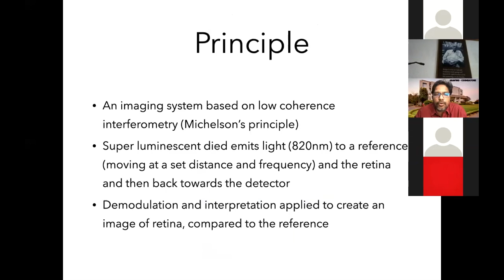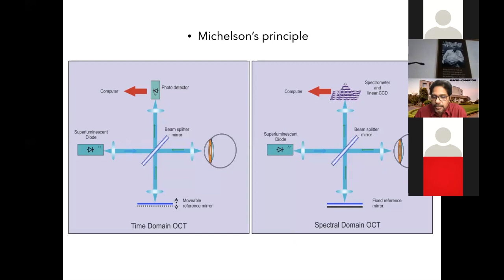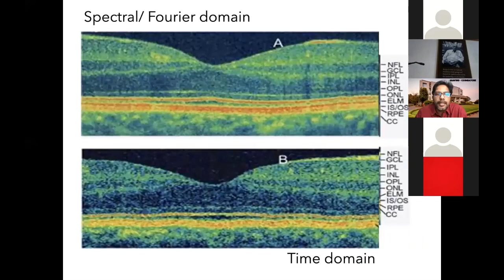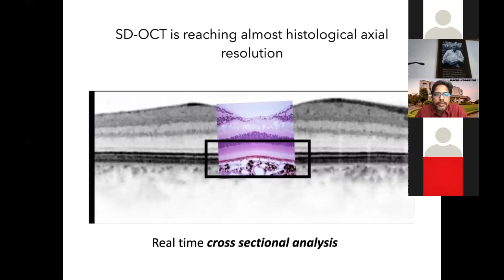The main principle is that it uses Michelson's principle, where light rays from the superluminescent diode are sent to the eye. The difference between time domain and spectral domain is that there is a fixed reference mirror in the newer systems, enabling us to give much faster acquisition of images as well as higher resolution. Just to show the difference between the time domain and spectral domain, you can see the difference between these two.